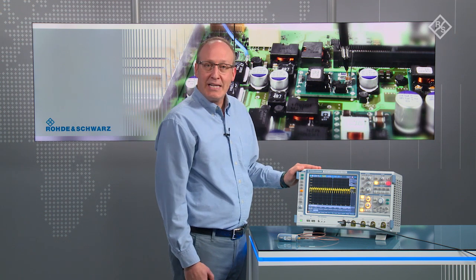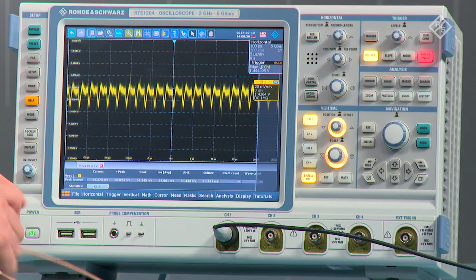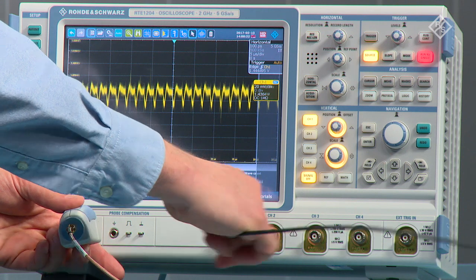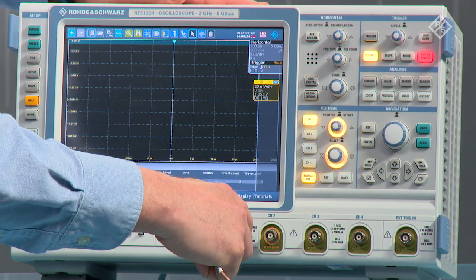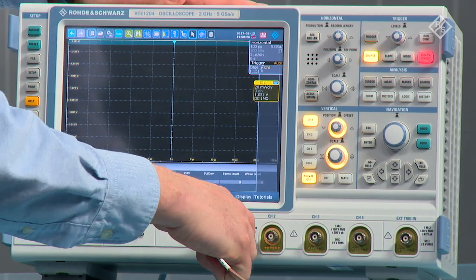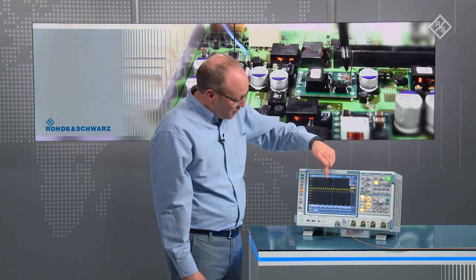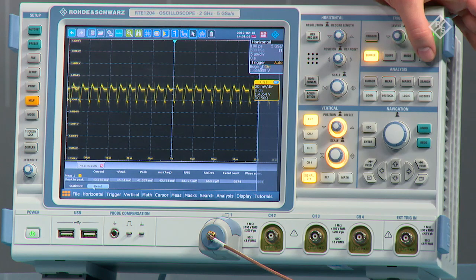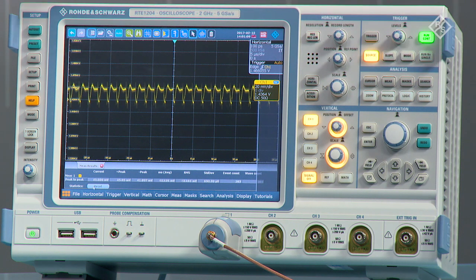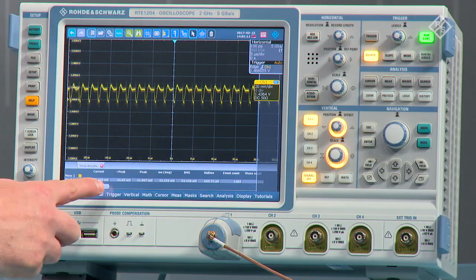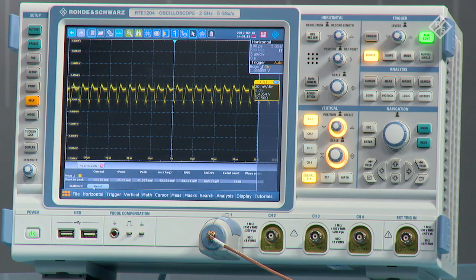Let's go ahead and switch to a nicer probe using the ZPR20 power rail probe. With the ZPR20 power rail probe connected, we see a much cleaner signal with very, very little noise. If I press single, it looks very, very sharp and clean. And you can see that the amplitude measurement has been reduced to about 46 millivolts.